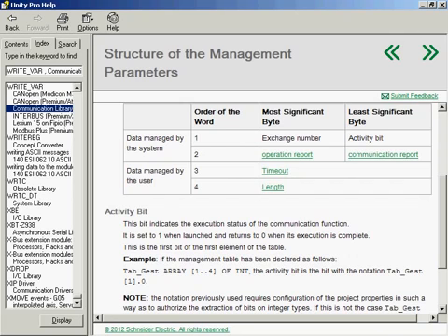So the fourth word of this array is the length. This is written again by the PLC. It is the length in bytes of the communication exchange. So if we're writing or reading 10 words, this length will be 20. So let's program the read VAR.